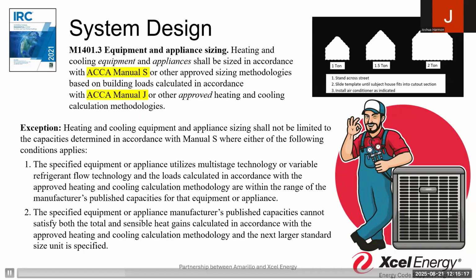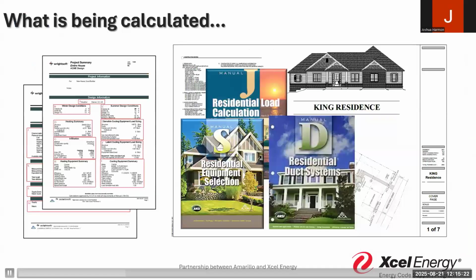I'm going to need some kind of manual J calculation to say this does match the design. As an inspector, I'm not recalculating that number - what I'm verifying is that the conditions that existed in it are still applicable. Now a lot of this is done by plan review, but some of this I'm going to be double-checking when I'm in the field.